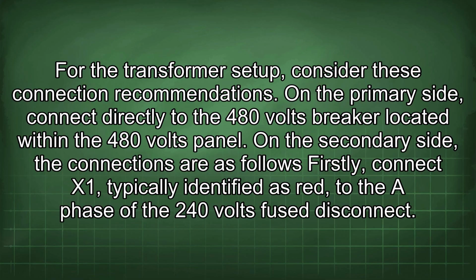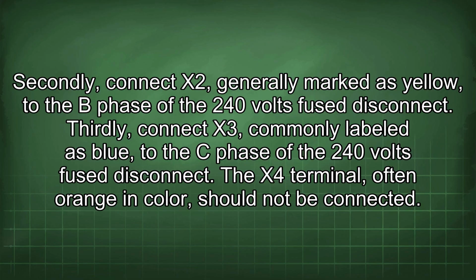Firstly, connect X1, typically identified as red, to the A phase of the 240 volts fused disconnect. Secondly, connect X2, generally marked as yellow, to the B phase of the 240 volts fused disconnect. Thirdly, connect X3, commonly labeled as blue, to the C phase of the 240 volts fused disconnect.